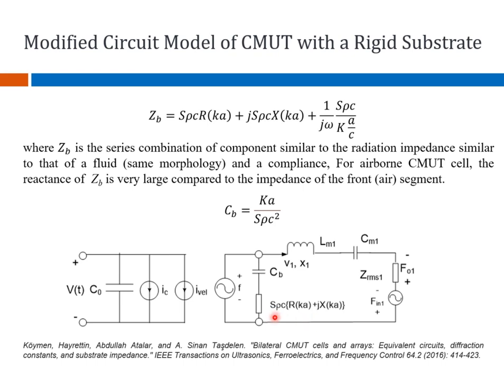And this loss, you can say, the RC loss, is representative of the backing loss, the vibrations of the ultrasound that is being emitted at the same frequency but at longer wavelengths in the backing materials. Why are they longer wavelengths?